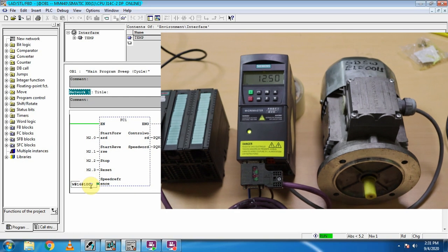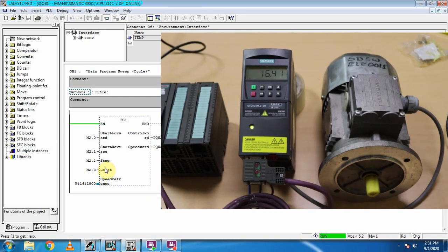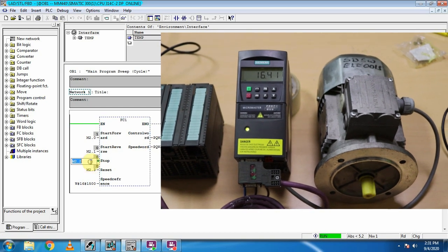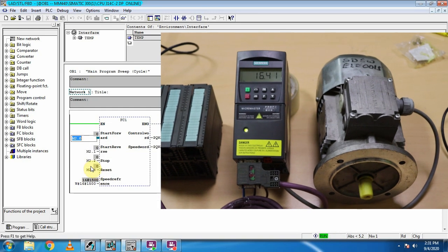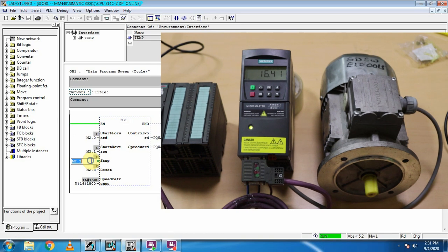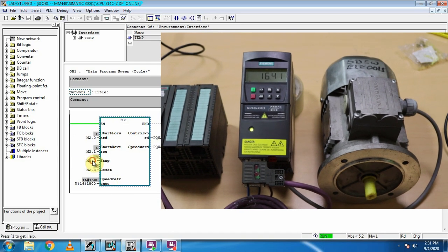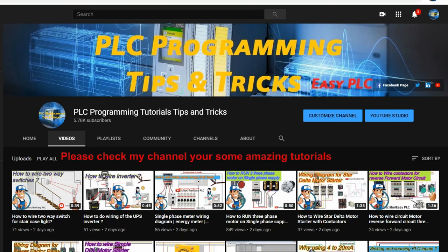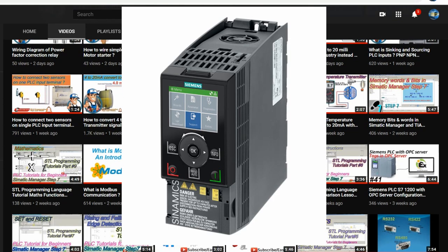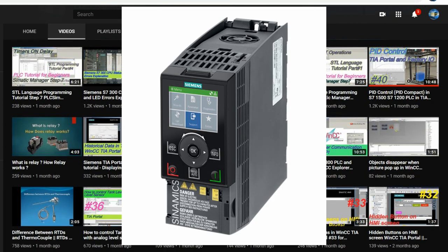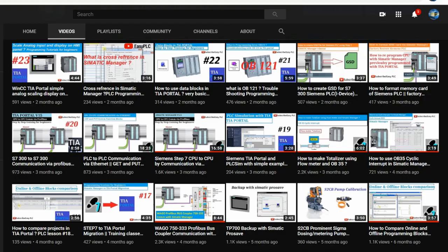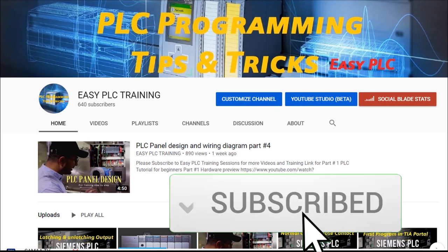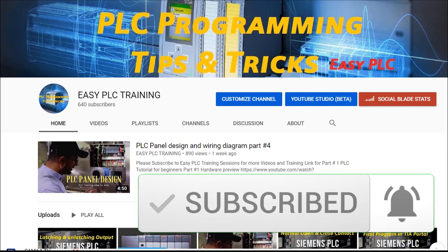We can also change the speed of the motor — entering 1500 gives approximately 16 Hz in the VFD. As you can see, our VFD and PLC are communicating together and we can turn the motor on and off using the start and stop bits. Today we created basic code in Simatic Manager to connect the PLC and Micromaster 440 VFD via Profibus. In upcoming videos we will use the Sinamics G120 drive and communicate with the Siemens PLC using MPI and Ethernet ports. Thanks for watching — please subscribe to the channel, and until next time, take care and goodbye.